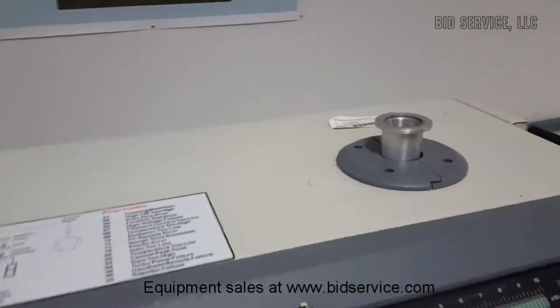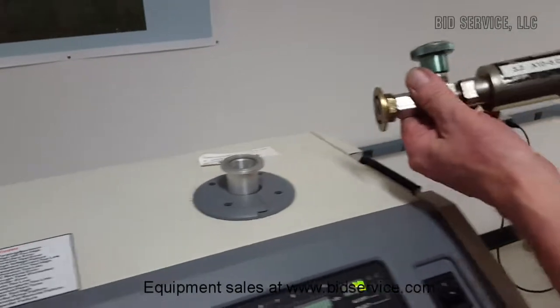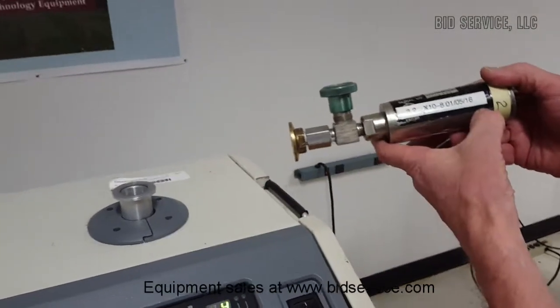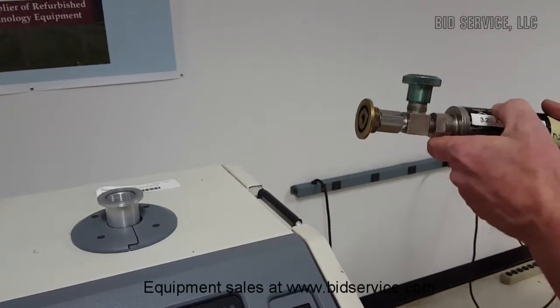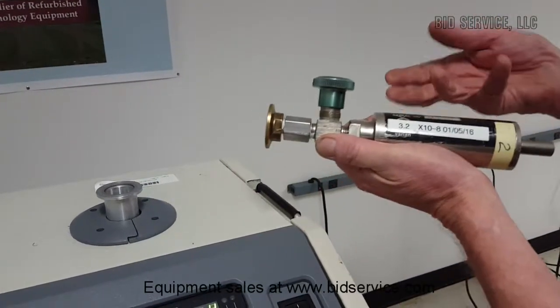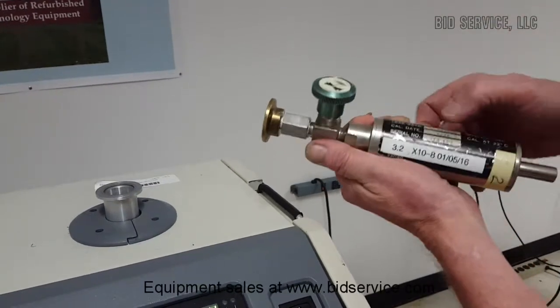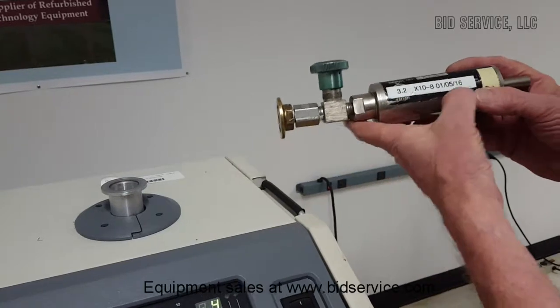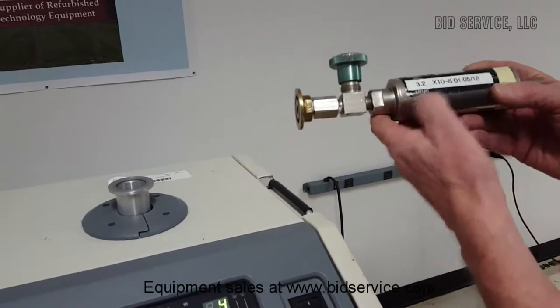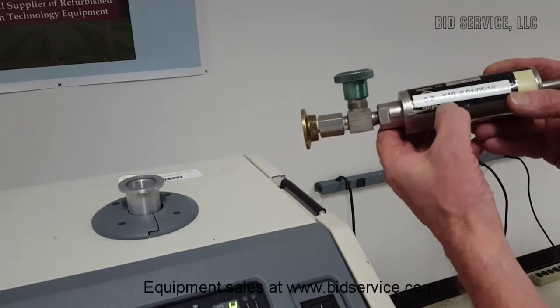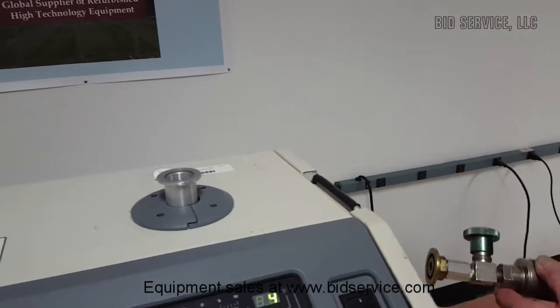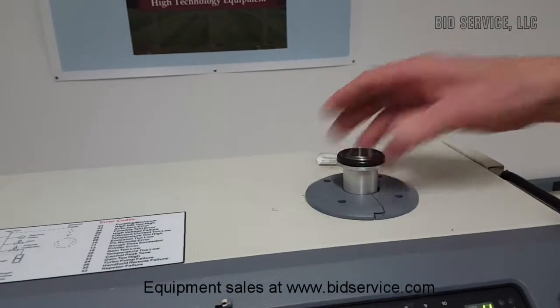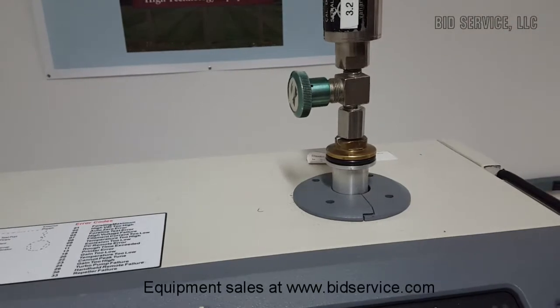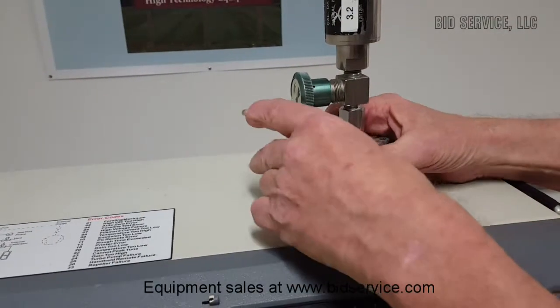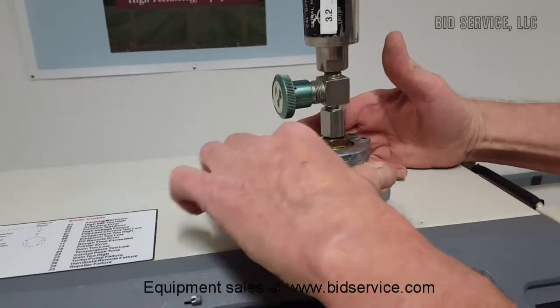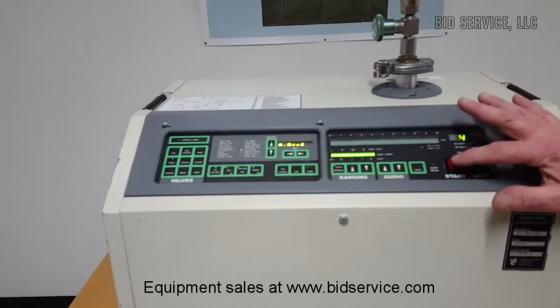What we're going to do is I have a standard here. Now we periodically check these standards, and there is a depletion rate, and what this depletion rate does is every year that you use this, there's a certain amount that will deplete from the original value. This one has been rechecked. I personally did this about a year and a half ago, and it's 3.2 times 10 to the minus 8. So we'll put that up here, just like this. Clamp it. And now we're going to pump down by hitting the start button.